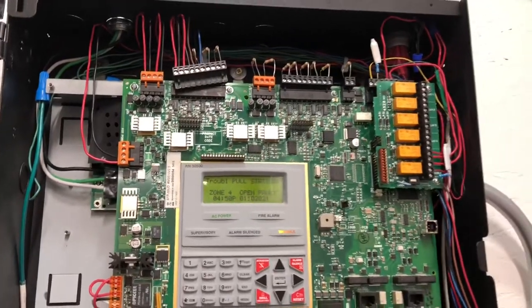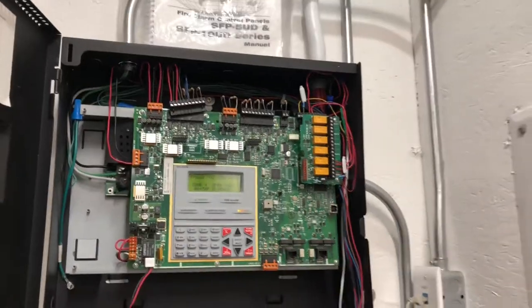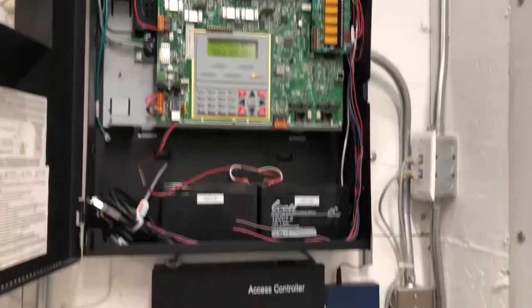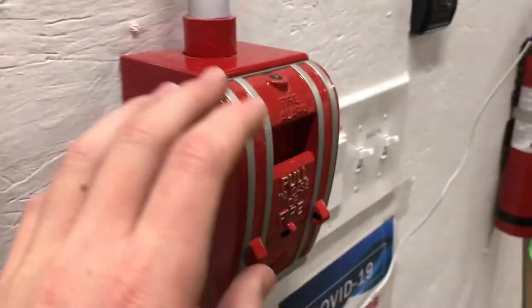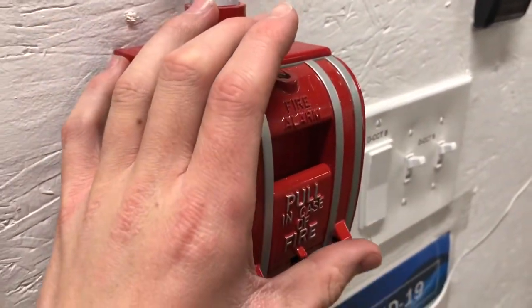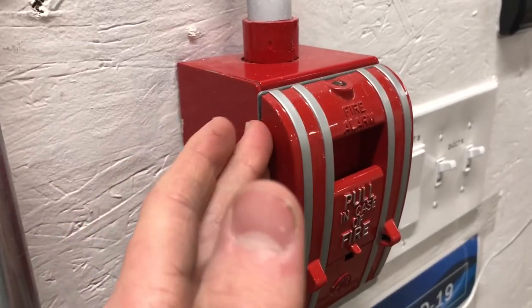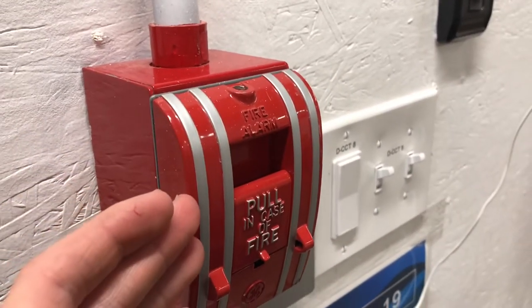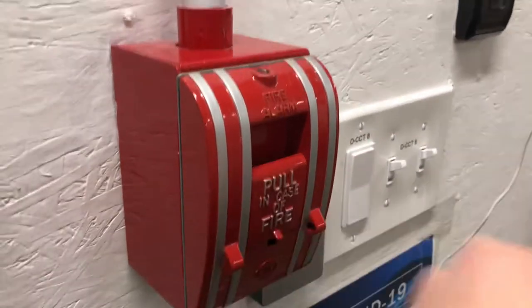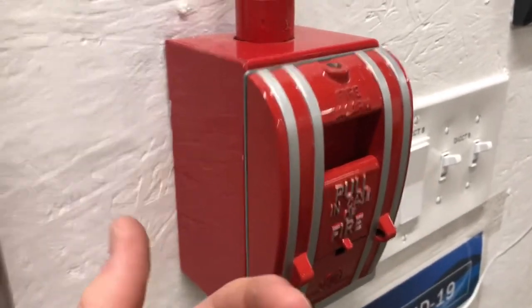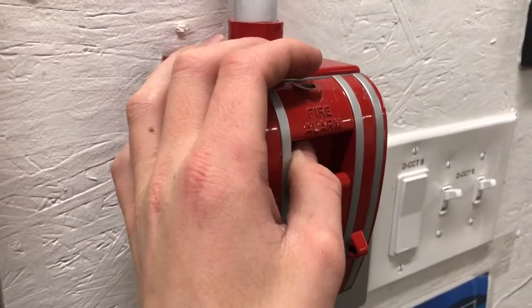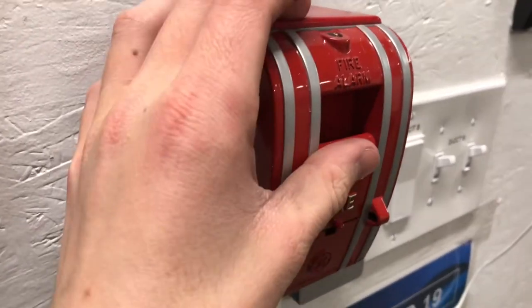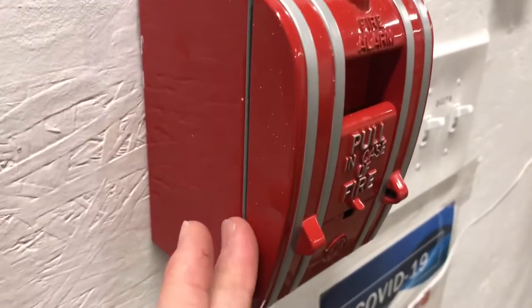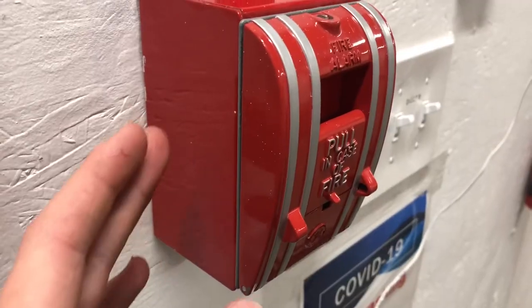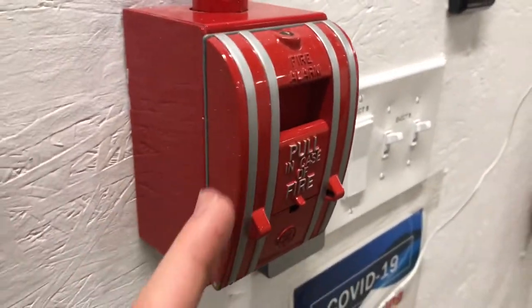So what I do now, now that you've determined what zone or output of the panel it's on, is start looking at your field devices. So now this is your first device. It doesn't matter how many we have, but you can take apart that device and then meter the outgoing side of it or the incoming side of it to see whereabouts that ground fault is. But if there's lots of devices, you may want to go to every other device or every third device, but let's open this one up so I can demonstrate what you do.